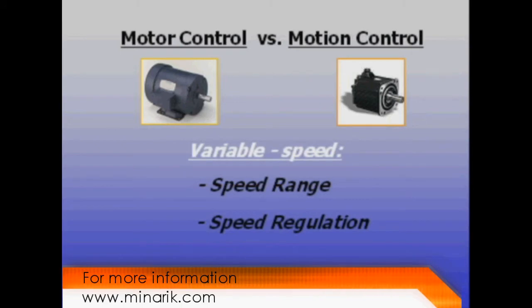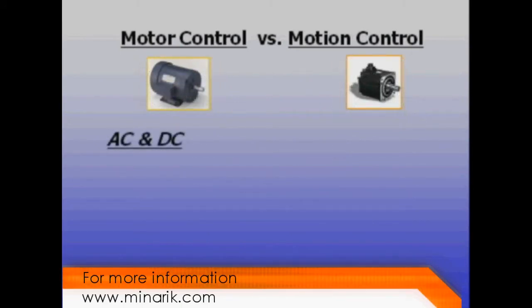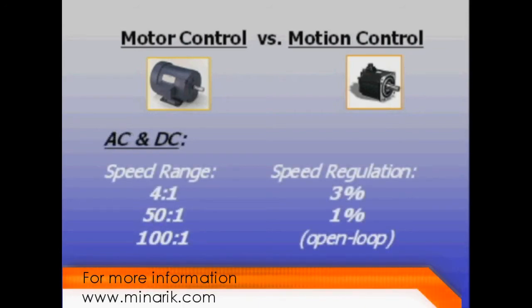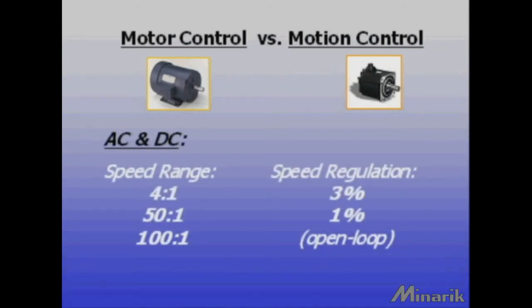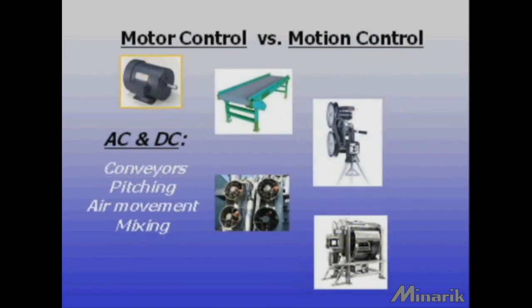Speed range and speed regulation are the key performance measures. AC and DC motors and drives work well for applications under 50 or 100 to 1 speed range and speed regulation of 3 to 1% open loop. Examples include conveyors, pitching machines, air movement, and mixing.